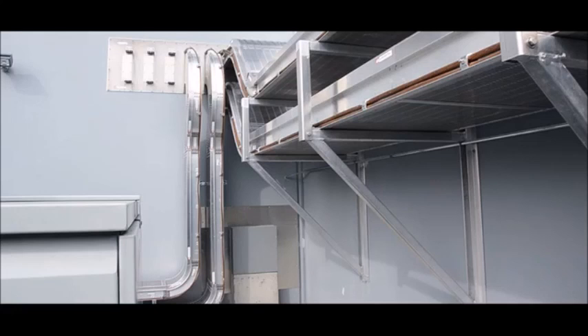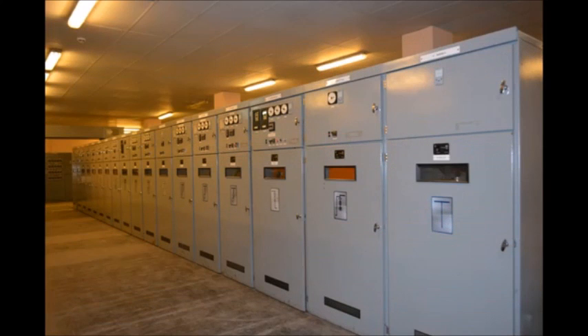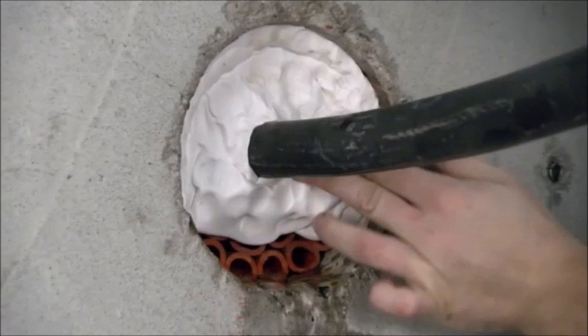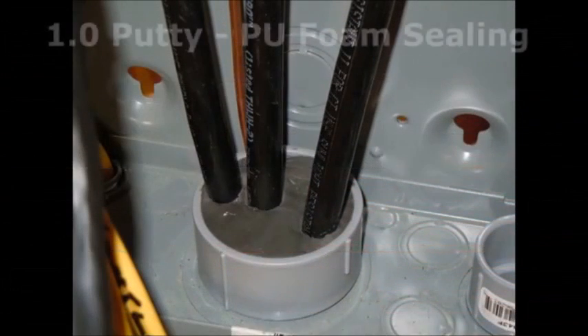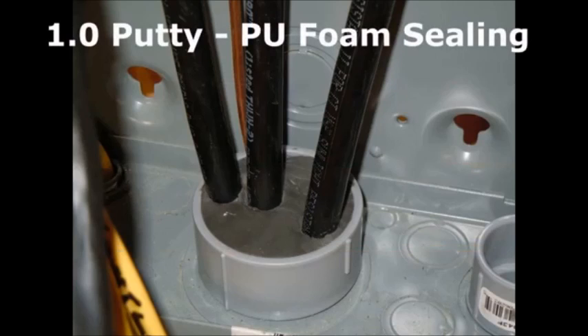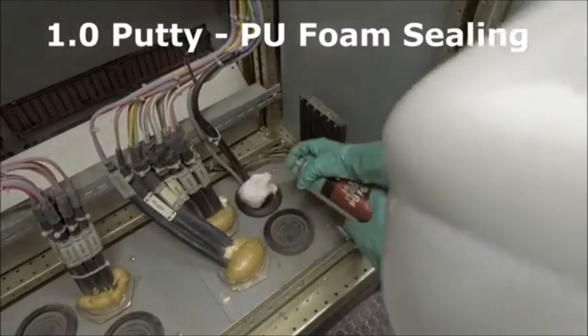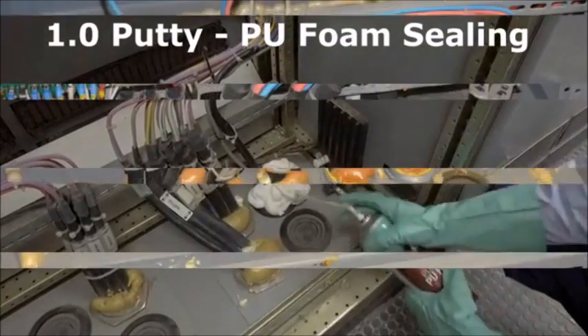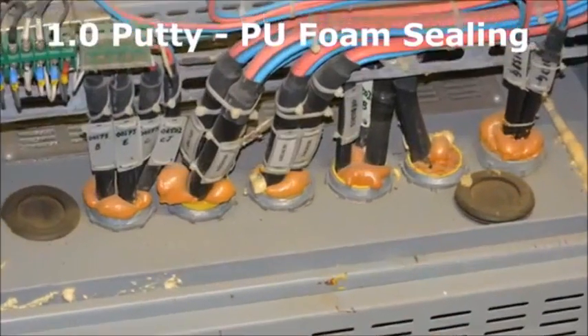Corrective and preventive measures. Preventing ingress of these reptiles in cable trenches, conduits and cable raceways was the only viable option in this scenario. Four preventive and corrective actions were adopted in this regard. All openings from cable raceways to the 6.3 kV breaker's room were sealed with putty sealant along with polyurethane foam. A similar methodology was also applied at other breakers' cubicle switchgears of the plant.